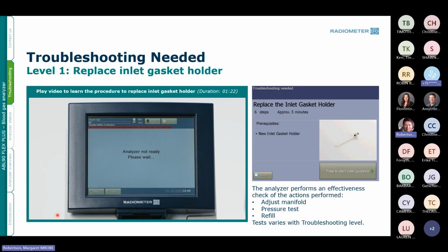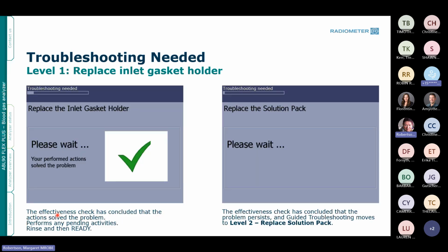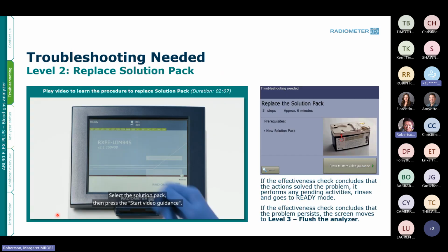Now the nice thing about the video that you've seen here, if you look to the right with that screen where it says Replace Inlet Gasket Holder, you'll also see that there's a video tutorial on board the analyzer. So it will walk you through the steps of replacing that inlet gasket. It walks you through the steps for everything that you need to do on the analyzer. So this would be a level 1 in terms of troubleshooting. And again, at the end of it, it'll give you a check mark to let you know that everything was okay and the solution pack is back in place.